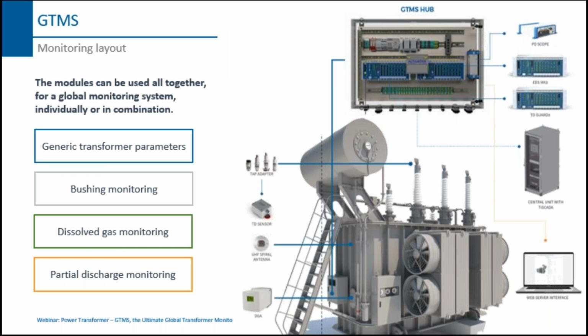Here you can see a picture with all the 4 modules installed: the generic transformer parameters, bushing monitoring, the dissolved gas monitoring, and partial discharge monitoring. The modules can be used all together for a complete system, or used individually or in a combination. You can see here some sensors. Here is the tap adapter. Sorry if the font is too small. That is normally installed on the bushing side. Then we have the tan delta sensor, and other sensors for partial discharge detection, like a UHF spiral antenna, then a DGA unit. On top, you can see the GTMS hub, where we can have all the acquisition units installed in a box with IP66 or IP68 degree.